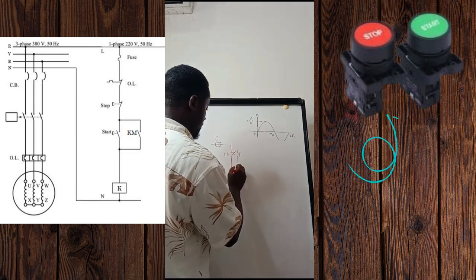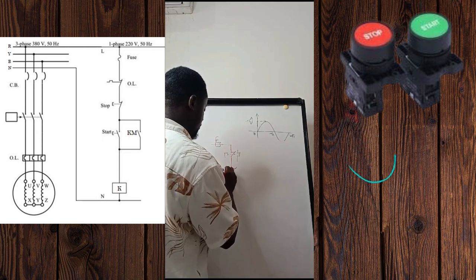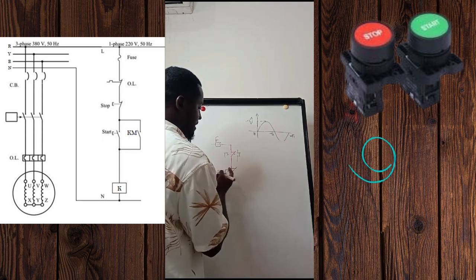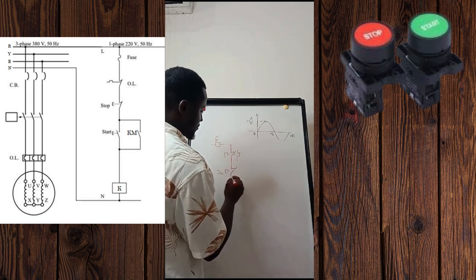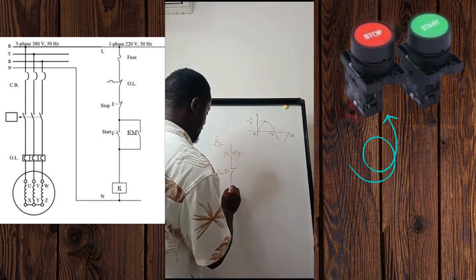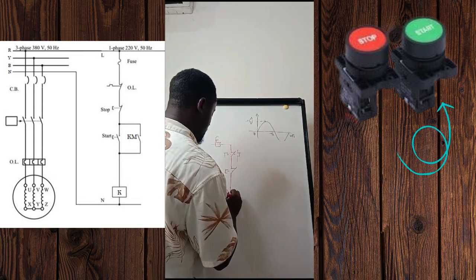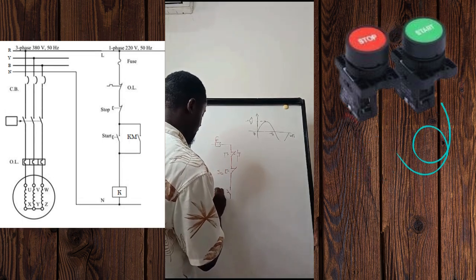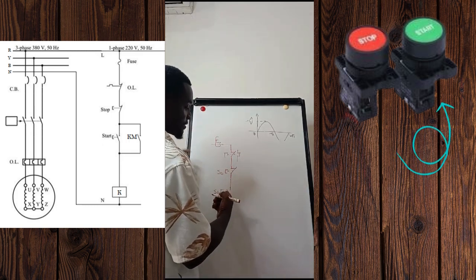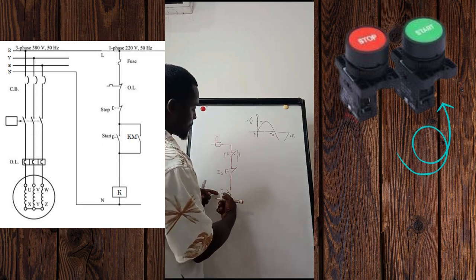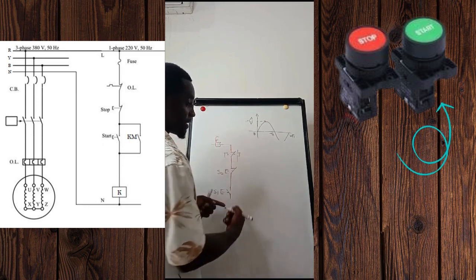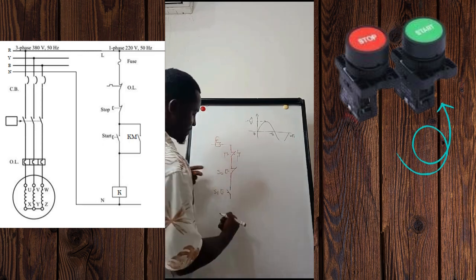Next we are going to have our stop push button, which I'll call S0. It is a stop push button with a normally closed contact. Then we move to our start push button, which is S1. This is the start push button, and that's the reason why we use a normally open contact — so that when we press it, it closes to allow current to flow from upstream going to downstream.